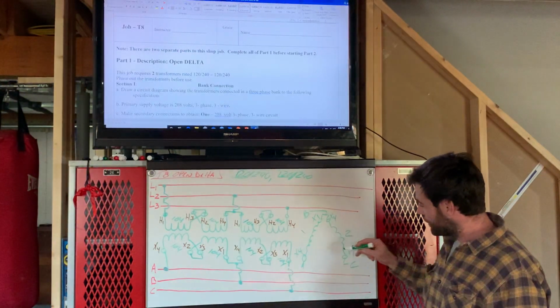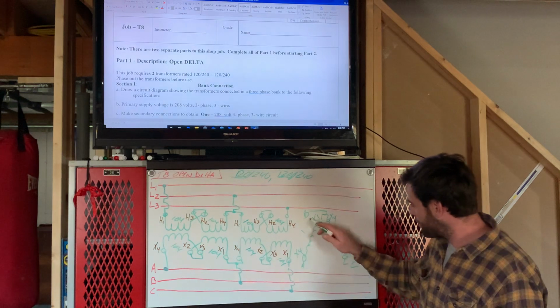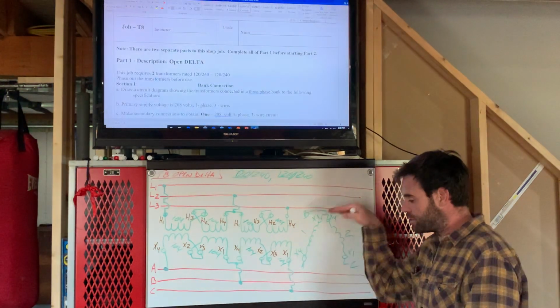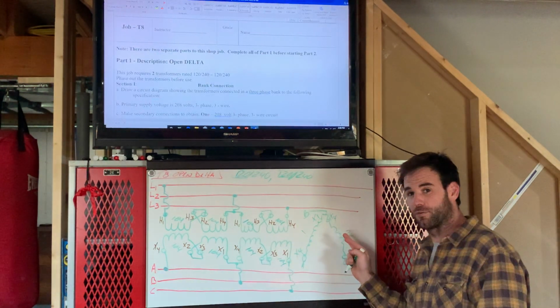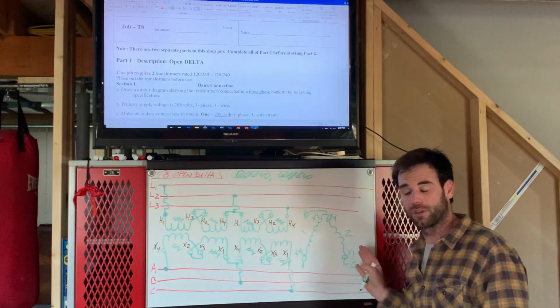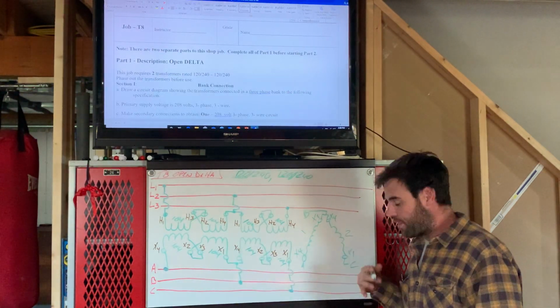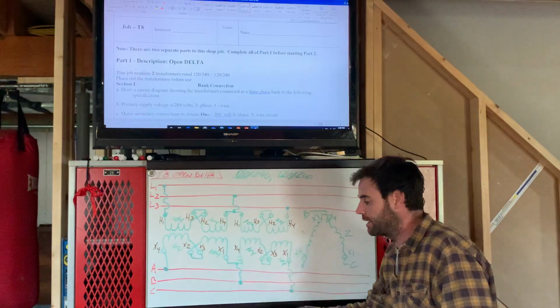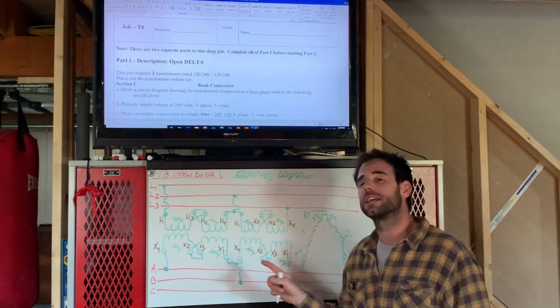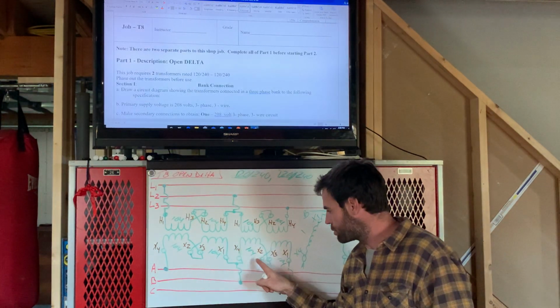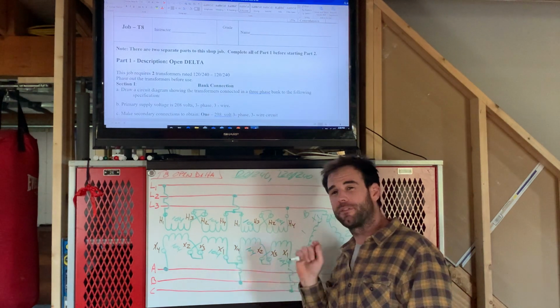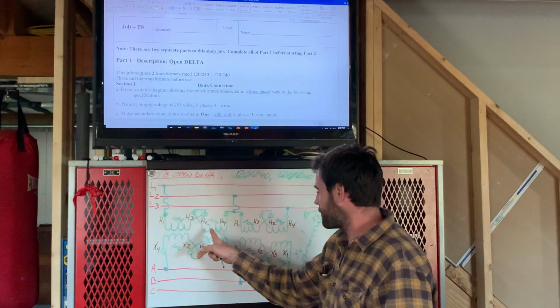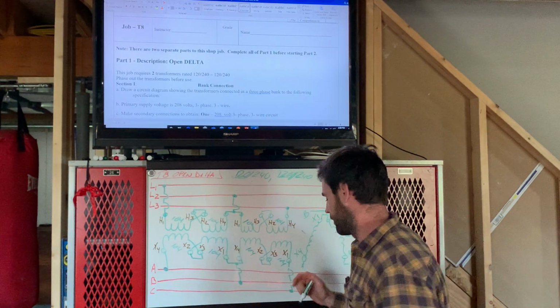So, because of this, we're producing three-phase power, A, B, and C, except we're going to have to reduce the kVA capacity of this transformer bank, because you're not going to be able to get the full kVA capacity out of this. The numbers, again, we'll cover this. It's either 86.5% of 2 transformers, or it's going to be 57.7% of the original 3. We'll cover it, all right?